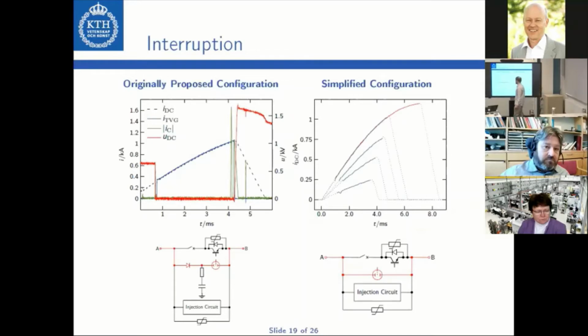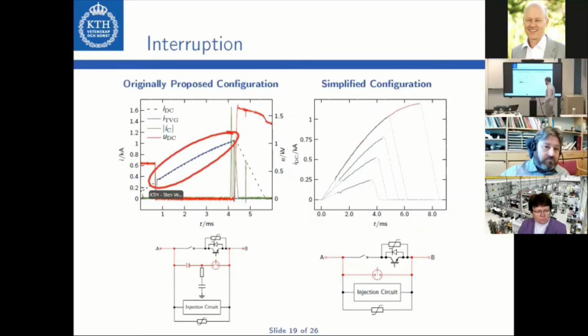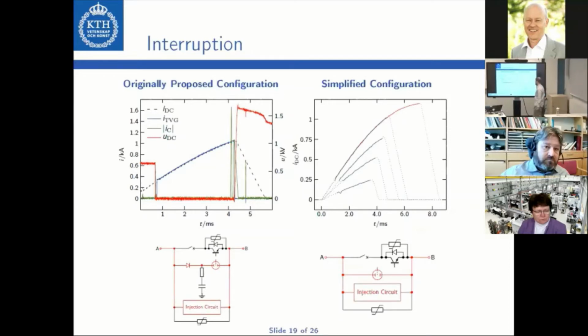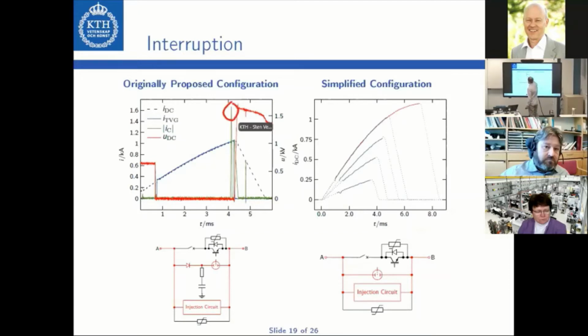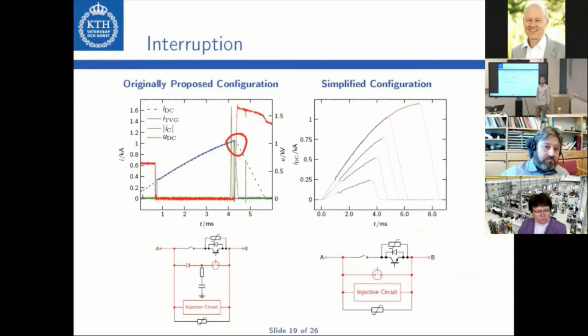In this state, the triggered vacuum gap conducts, which you can see with this blue line here. And it conducts for a while until the current in the DCCB exceeds the trip level. At this point, the injection circuit is activated. The implementation for the injection circuit we use in the lab first causes a current pulse in the opposite direction, and then a second current pulse in the correct direction, which then causes the artificial current zero crossing in the triggered vacuum gap, and hence gets rid of the discharge and turns it off.